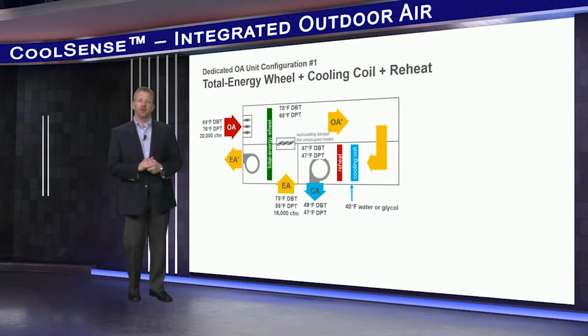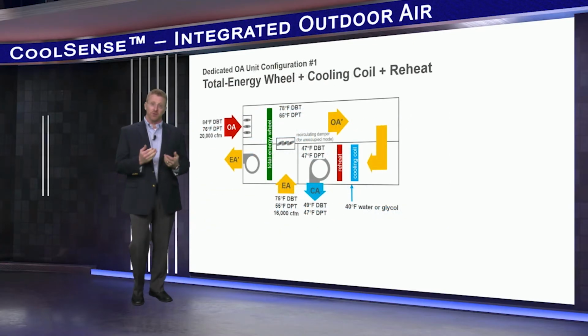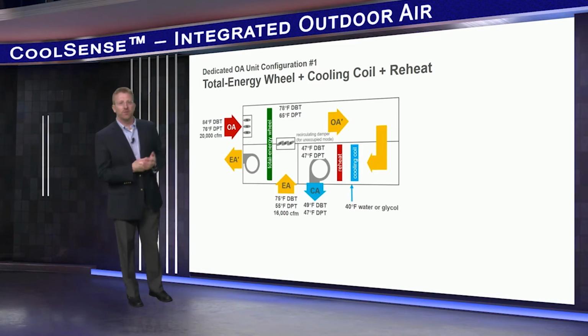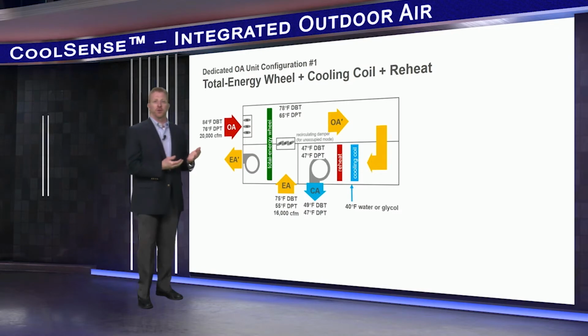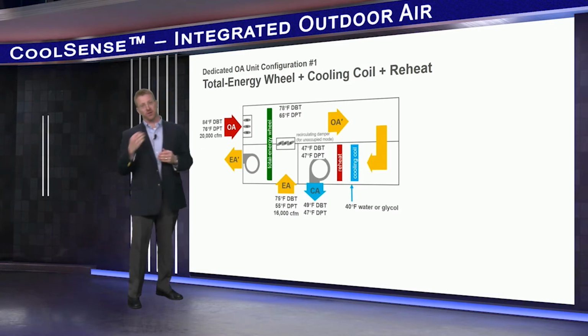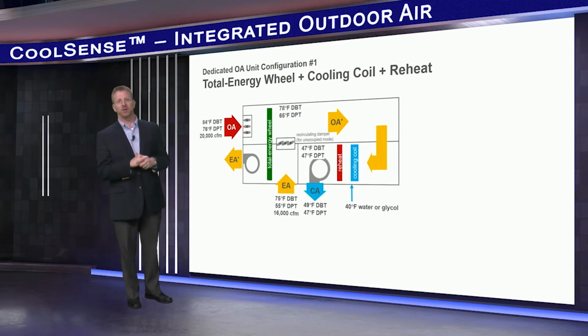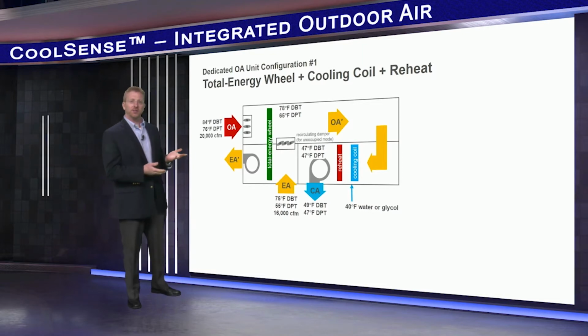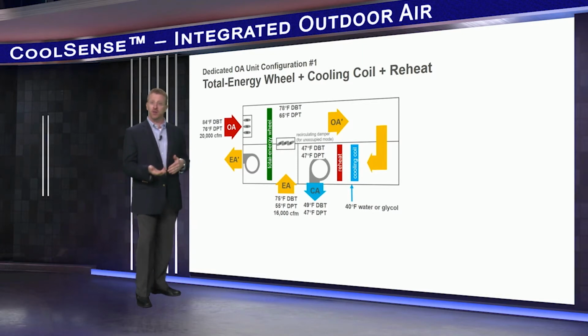Using that example then of 47-degree dew point for an office space, now we'll look at a few dedicated outdoor air unit configurations that can be used to dehumidify the outdoor air to this required dew point. The first configuration uses a total energy wheel to precondition the entering outdoor air by exchanging both the sensible and latent heat between the outdoor and the exhaust air streams. The air then passes through a cooling coil and possibly a reheat coil before the fan discharges it into the ductwork.